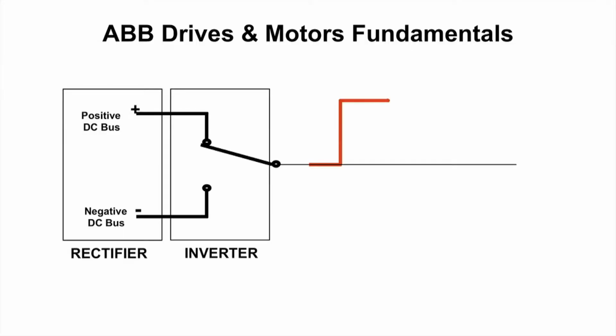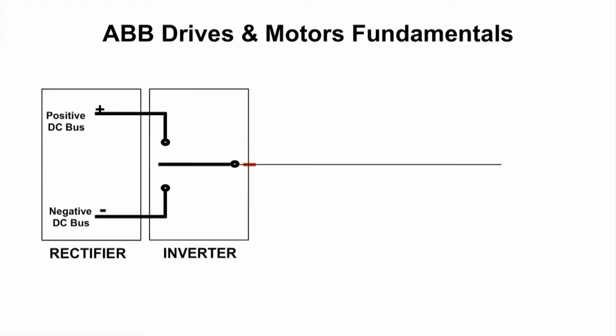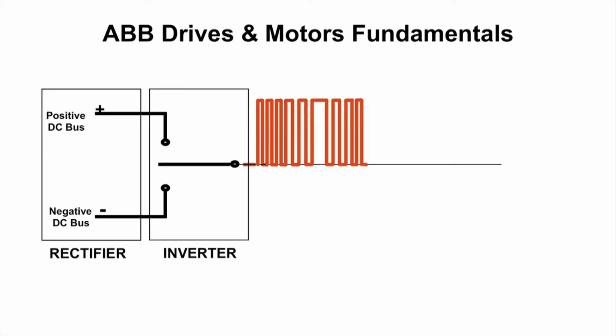So every time we turn on a transistor, it conducts electricity to the positive side, and we send out a pulse of energy to the motor. And then we turn it off again, and it goes back to 0. Then we turn it on again, and it goes to the negative side, to negative voltage, and off again, back to 0, on again, off again. So that sort of approximates a sine wave when we get done. In reality, it does it thousands of times a second, and it does the same switch on, on again, on again on one side. And then when we get wide enough, you'll notice the pulses are getting wider. That's the pulse width modulation. That is part of a VFD.